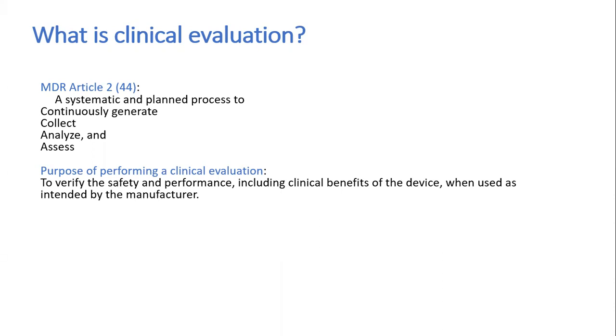Any product which is not there in the market, or there is some novel design, we go for several steps like clinical investigation and trials, and we see to it that there is no residual risk. And if any residual risk is there, and if we need to perform corrective and preventive actions, we perform them. And then we provide the evidence that we have taken all measures to see that the product is going to be safe for the patients. So the main purpose of clinical evaluation is to demonstrate the safety and performance.